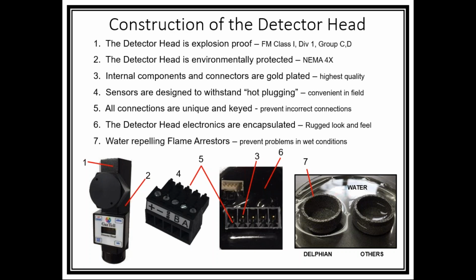The last thing that I think is unique to Delphian is that we have come up with a proprietary method of treating our flame arresters so that they are anaerobic, which basically means that it will repel the water, whether it be rain or condensation. One of the enemies of a gas detector is that you can't allow water to get to the inside of the unit, because with a catalytic bead, it'll short out the beads. With an IR, water and water vapor actually absorb light. And if they absorb light, it's going to look like an actual gas leak.